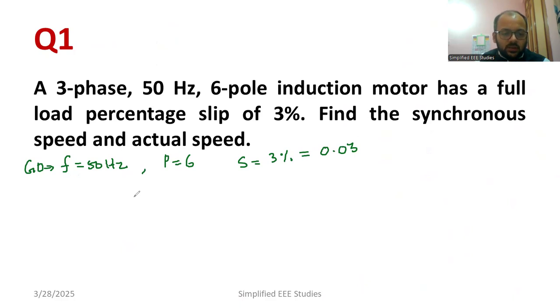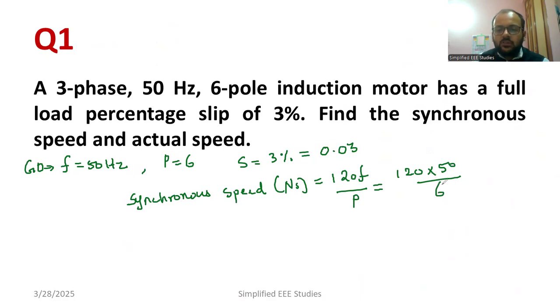You need to calculate the synchronous speed. The synchronous speed is the speed of rotating magnetic field, given by Ns = 120*F/P. Substituting the values: 120*50 divided by 6, this becomes 1000 RPM. That's the right answer.